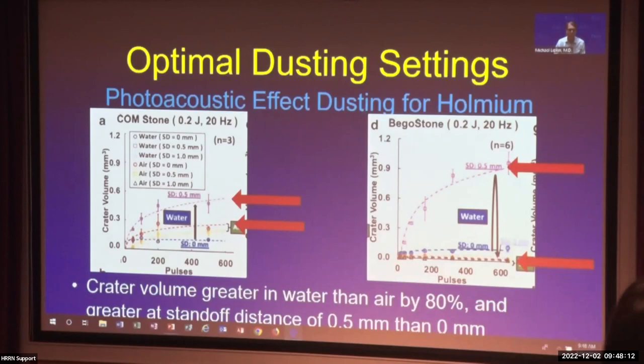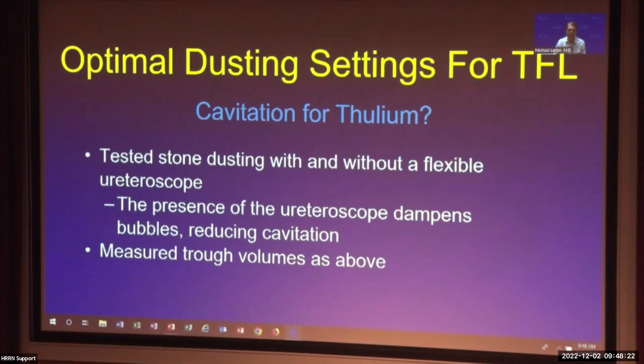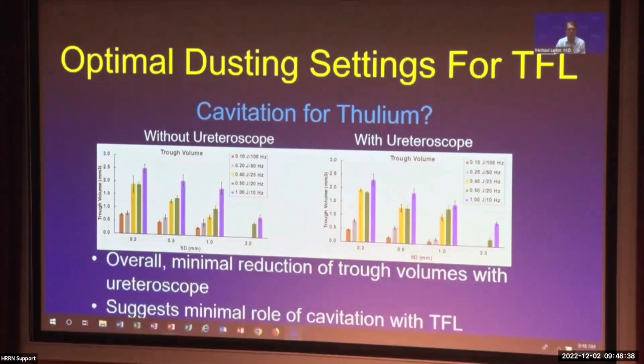For the thulium laser, we tested dusting with and without a flexible ureteroscope close to the laser tip — the presence of the ureteroscope can dampen bubbles and reduce cavitation. We found that irrespective of the ureteroscope, trough volumes were very similar with very minimal difference, suggesting that with the thulium laser there is minimal role of cavitation and it's primarily a photothermal effect. The mechanism is different, which is why the settings need to be so different.